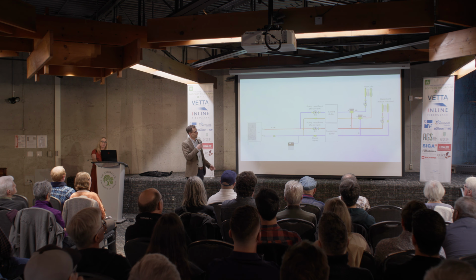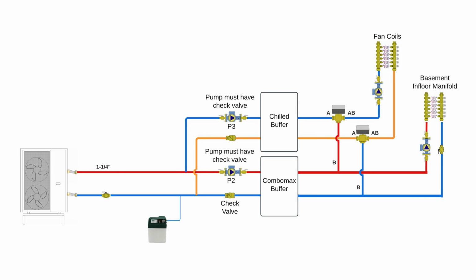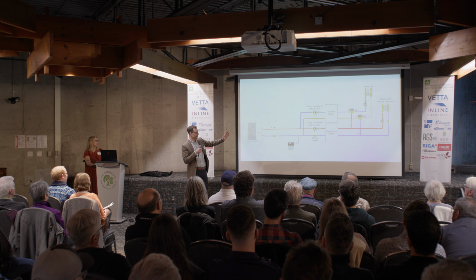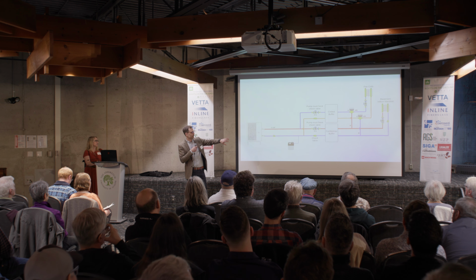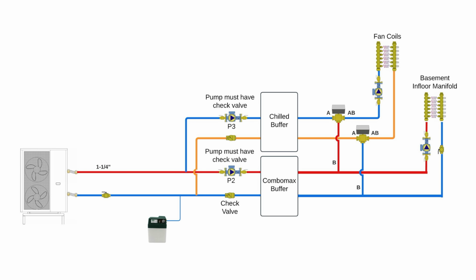Here's a simplified hydronic diagram for the building. So again, this is a monoblock air-to-water heat pump, which means it's built in a factory. It has a self-contained refrigerant system. When it arrives on site, what we do is connect a control wire to tell it what to do, a power wire to send power to it, and then there are 2 pipes, a supply and a return. No refrigerant goes past that point into the building. So we run a glycol water mixture outside to that unit. It only does one job. It makes hot or it makes cold, and it sends that water back in.